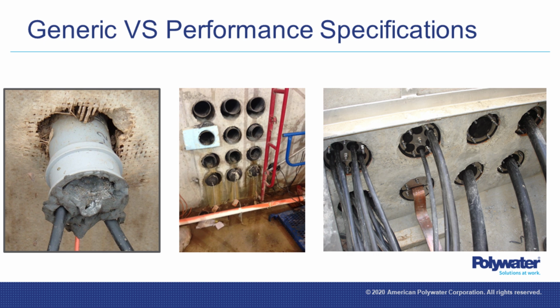But when you oversize conduit and your cables become cradled, so all 3 cables are laying side by side in the bottom versus triangular where they're stacked, you have more rub. When they're triangular, you only have 2 places of rub. But the biggest one to factor in is if you have bends and 90s in your system, and let's say you do short radius bends, it's not a problem because you can figure it out. So this is super overcomable in the field. By doing that calculation, it will tell you how much jamming could occur, whether there's no problem or if jamming might occur. And it usually happens through short radius bends, not long sweeping bends.